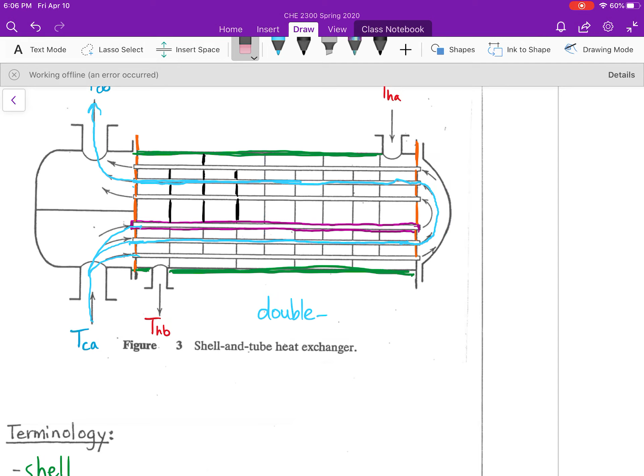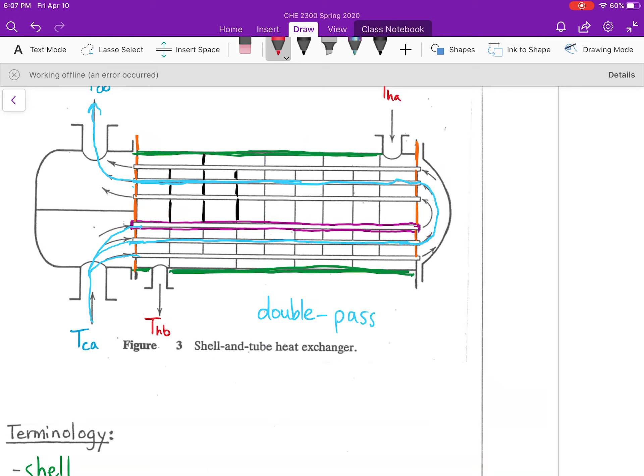It's a double pass because the fluids make two passes through the heat exchanger. In this example, the double pass comes from the cold fluid making two passes. Technically, the hot fluid is not making two passes - it is just having its flow directed differently based on these baffles.